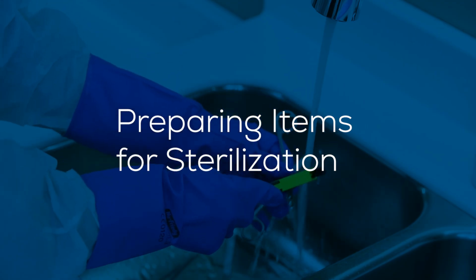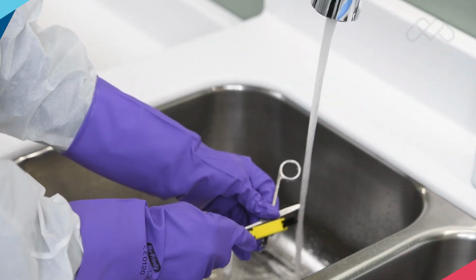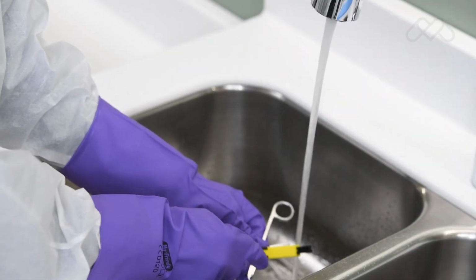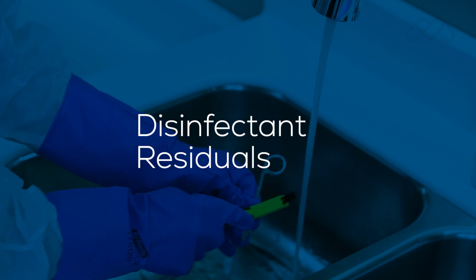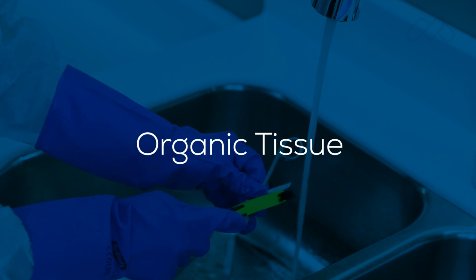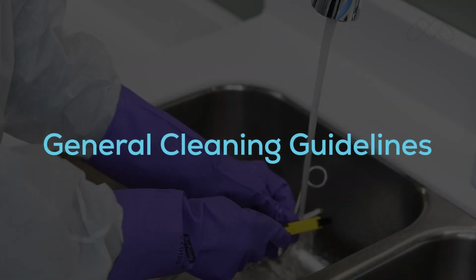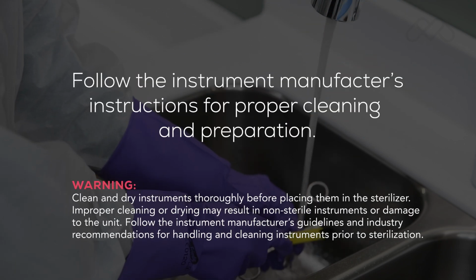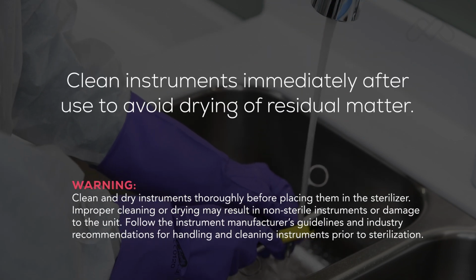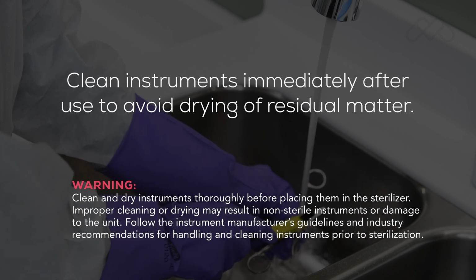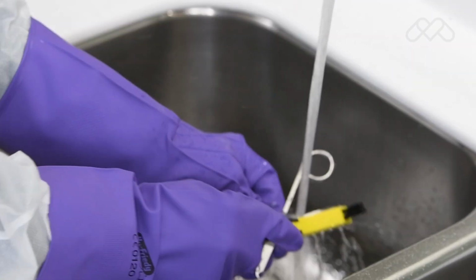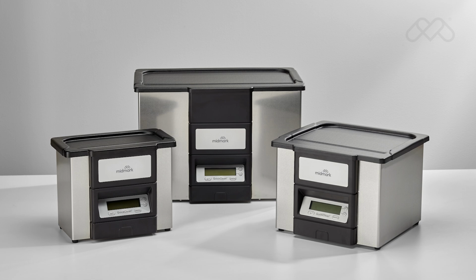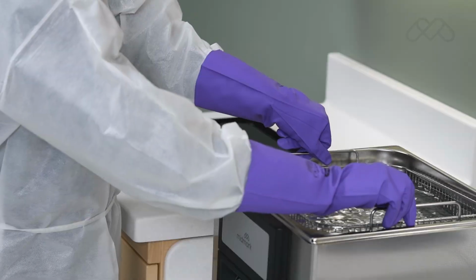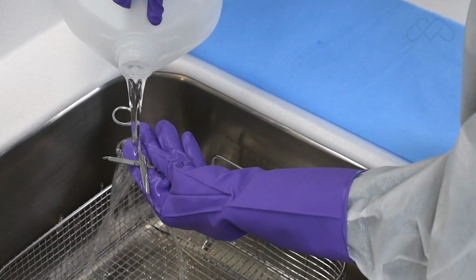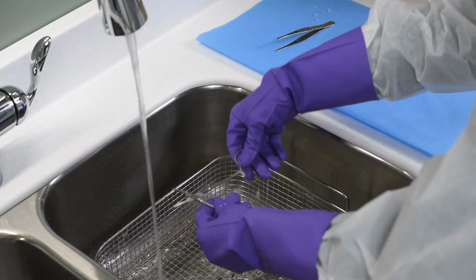Preparing items for sterilization. Instruments must be thoroughly cleaned to remove all residual matter such as debris, disinfectant residuals, blood, and organic tissue, for example. Follow the instrument manufacturer's instructions for proper cleaning and preparation. Clean instruments immediately after use to avoid drying of residual matter. The use of automated cleaning equipment is recommended in addition to manual cleaning for clinician safety and cleaning effectiveness. After cleaning, thoroughly rinse instruments with distilled or equivalent type water.